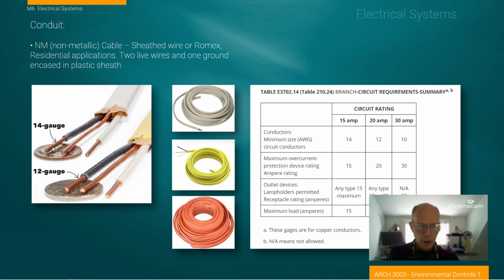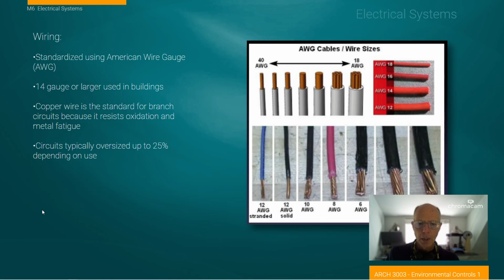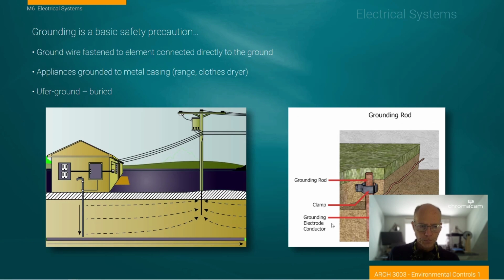So 14 gauge wire: a higher number means smaller gauge, less current; a smaller number means more current. This is 20 amp. So the numbers are moving in an opposite direction. A much larger conductor would be a 6 gauge or a 0 gauge, and that's illustrated here. So we have this idea of wire gauge and the idea that the numbers are really running in the opposite direction.